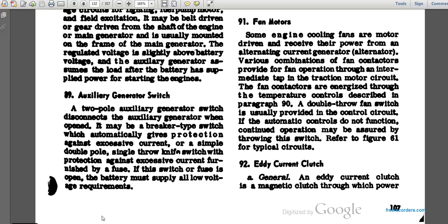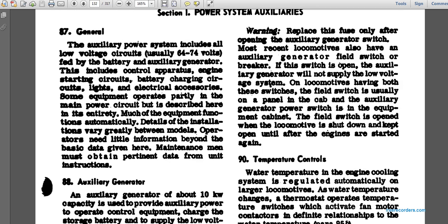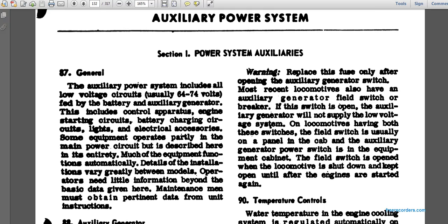A two-pole auxiliary generator switch disconnects the auxiliary generator when open. It may be a breaker type that automatically gives protection against excessive current, or a double-pole single-throw knife switch with protection against excessive current furnished by a fuse. When the switch or fuse is open, the battery must supply all low voltage requirements. Warning: replace this fuse only after opening the auxiliary generator switch.